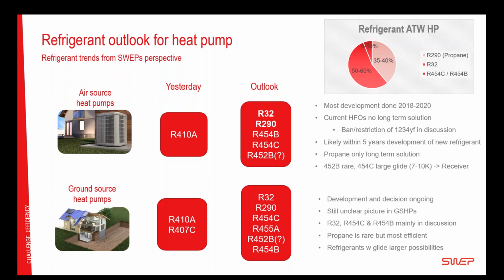If I go over to the ground source heat pumps, it looks roughly the same as the air source, but most of the developments are basically ongoing right now, and most decisions are not taken. Some are going to R32, it seems, some propane, and here the 454C should have a better possibility because it has a big glide, and it's much easier to handle in a ground source heat pump—you can actually utilize that glide. Propane will be a little less used here because you're indoors, though it can be solved with other safety measures. So there are companies using or looking at using propane. All this is developments right now, and we will see in a while where that lands.